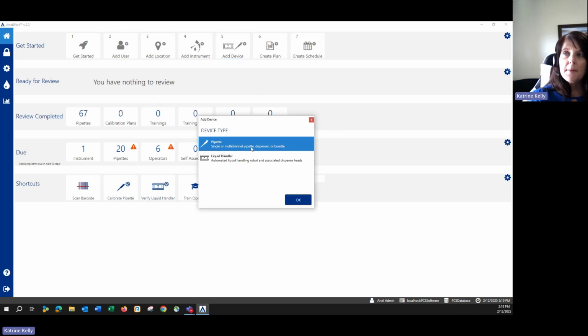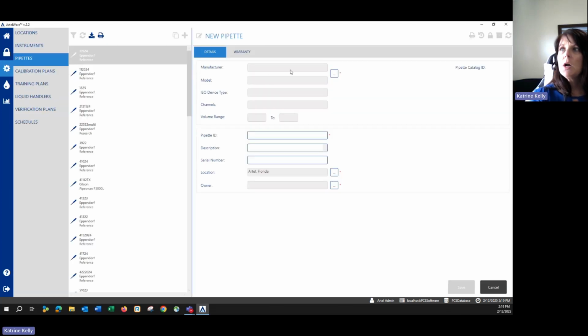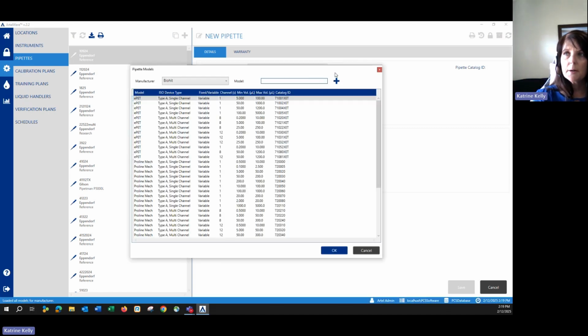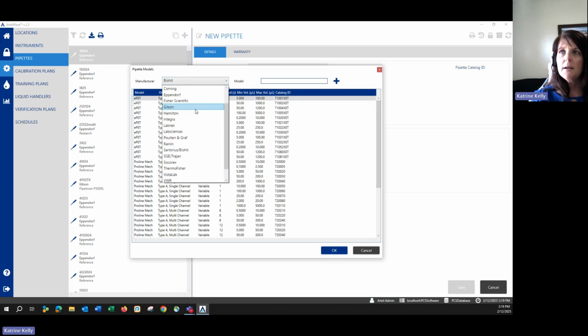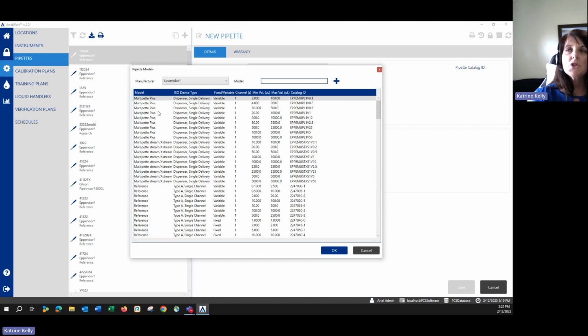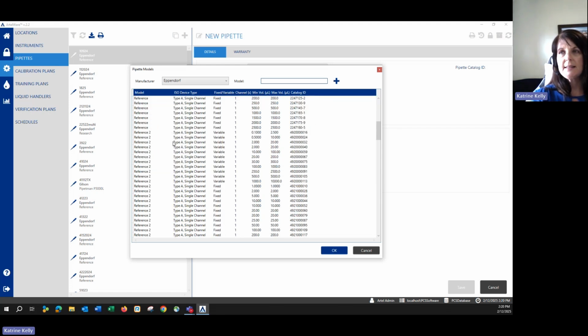And then you'll add your pipettes into the software. So to add a pipette, you'll click this little square with the 3 dots, the ellipsis over here. And once you click that, it brings up a list of pipette models and manufacturers that are already preloaded into the software for you. So you can see we have multiple manufacturers in here. So you'll select the manufacturer for the pipette that you have. And once you do that, the models for all of the pipettes that that manufacturer makes appear in the list.